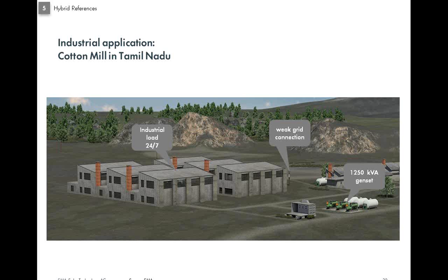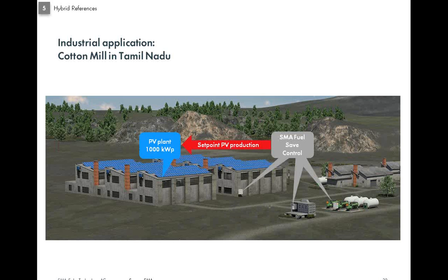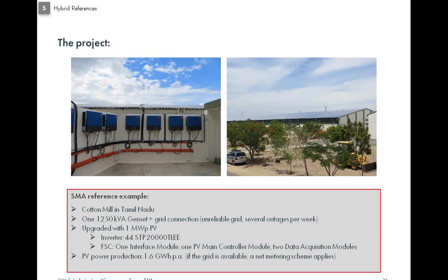This is a real life example of a cotton mill in Tamil Nadu where SMA installed a 1 megawatt system, and the modules were installed on the roof of the factory, as well as some modules on the ground also. These are the details of the project. There was a 1.25 MVA genset, and it was upgraded with 1 megawatt of solar along with the Fuel Save Control.